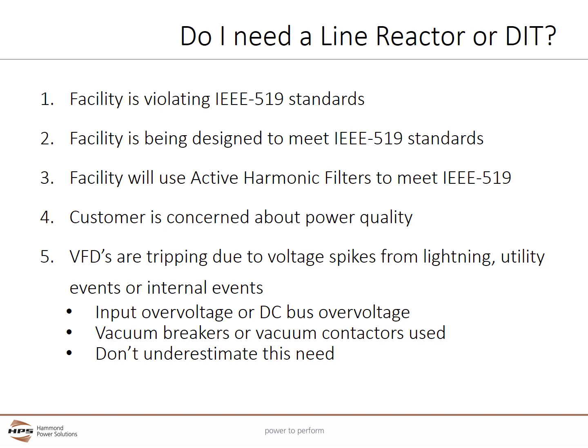Vacuum breakers or vacuum contactors can cause large transient voltage spikes. Facilities such as data centers often test these components, sometimes daily. Switching power factor correction capacitors can also cause voltage spikes, along with lightning. This issue should not be understated. These types of voltage spikes occur very often and can cause many problems in facilities. DITs and line reactors, along with equipment such as SPDs and lightning arresters, can do a great job in mitigating these issues.